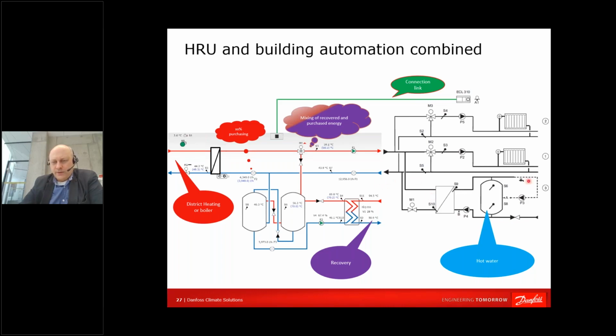When we are over with the domestic hot water, when it's not needed, we revert back to heating the air handling unit. There are also possible scenarios when we can close heating and ventilation during hot water preparation. If one of your circuits is supplying the air handling unit, then probably we might face somewhere here a heat exchanger, which is probably separating water from the glycol. So generally speaking, all that part is filled with ordinary water, not glycol. So that's how it works.